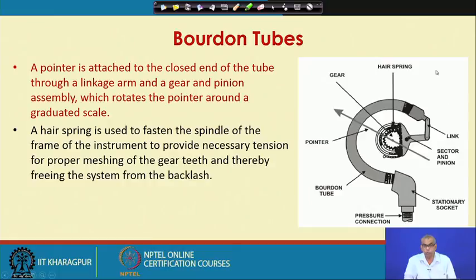So, what does the hairspring do? A hairspring is used to fasten the spindle of the frame of the instrument to provide necessary tension for the proper meshing of the gear teeth, and thereby freeing the system from the backlash. So, the hairspring eliminates or tries to eliminate the backlash in the instrument.